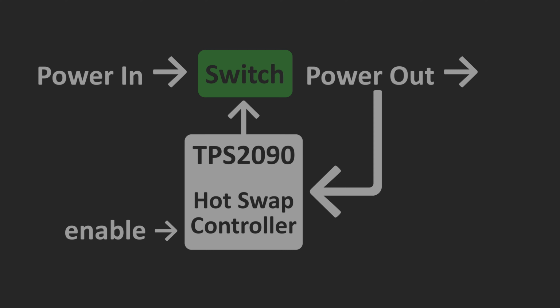The electronic circuit breaker is a particularly useful function of the hot swap controller. This controller is ultimately deciding whether or not power should be flowing to the downstream load, and it's doing this by constantly enabling or disabling a high side switch. In this case, that switch is a FET. This FET is a transistor capable of sourcing at least 50 amps to that load, and if we want the hot swap controller to enforce a current limit, we just have it monitor the voltage drop across a couple shunt resistors, and since we're working with so much current, we use 2.5 milliohm shunt resistors in parallel.